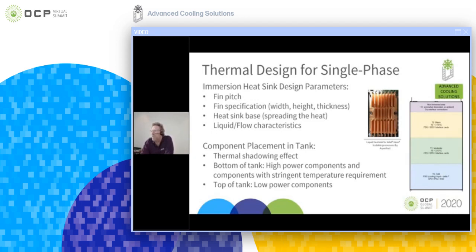Now, the liquid and flow characteristics are related to the fin positioning, fin design, and the angles in which the fins are placed, and these can differ per application. Another important consideration is the component placement in the tank. Thermal shadowing is something to take into account with single-phase applications. A component that is placed deeper into the tank that has a CPU, that has a second CPU in its direct path in an upwards direction, will create a thermal shadow, which means that the upper heatsink will be getting the preheated liquid from the bottom heatsink.